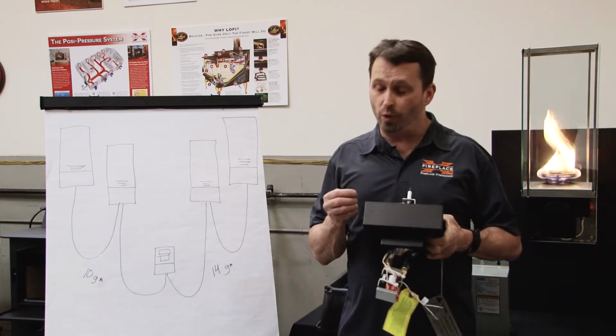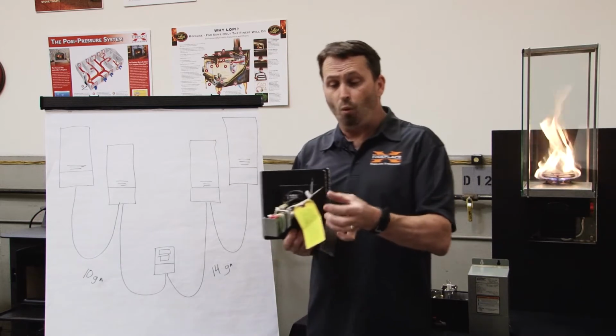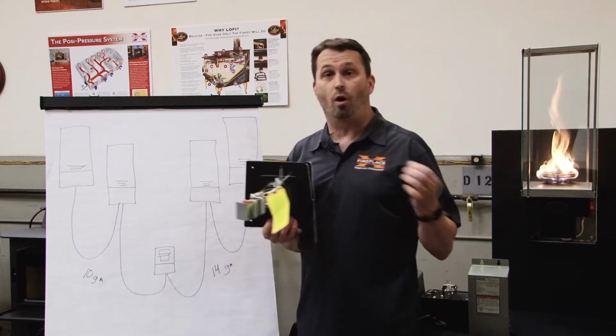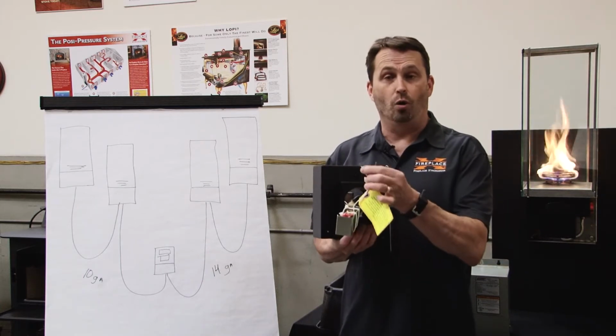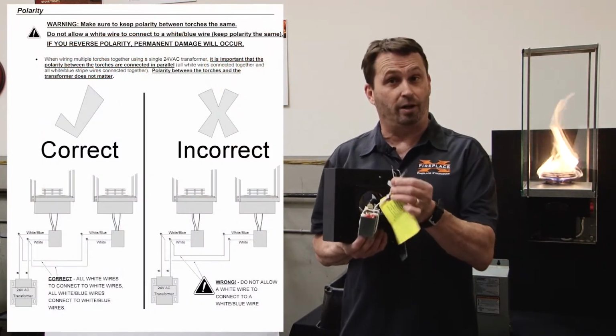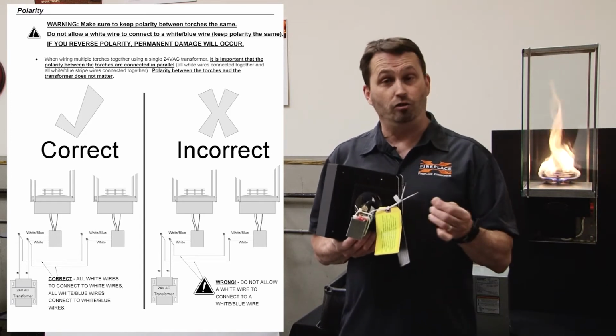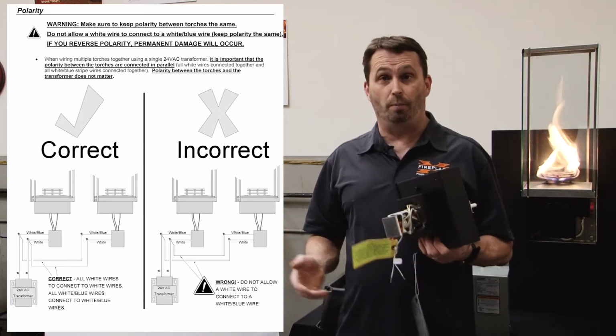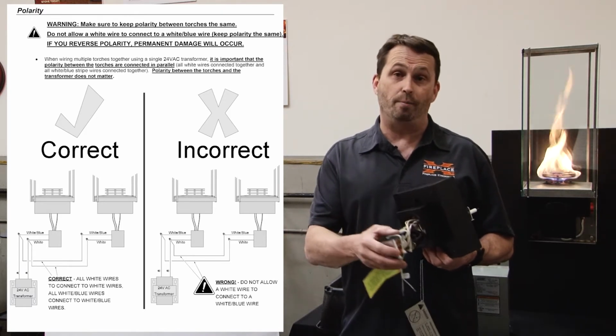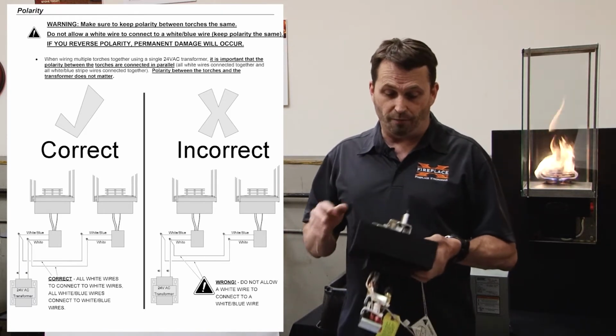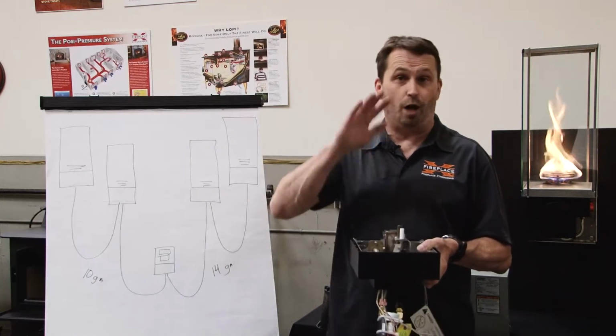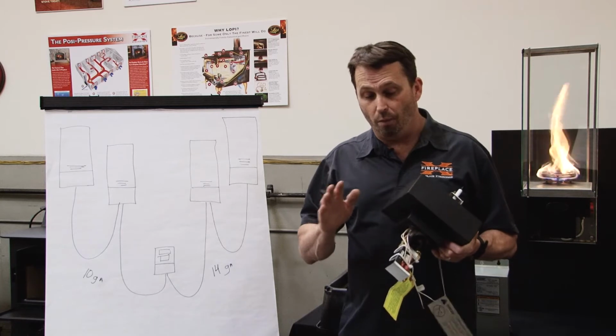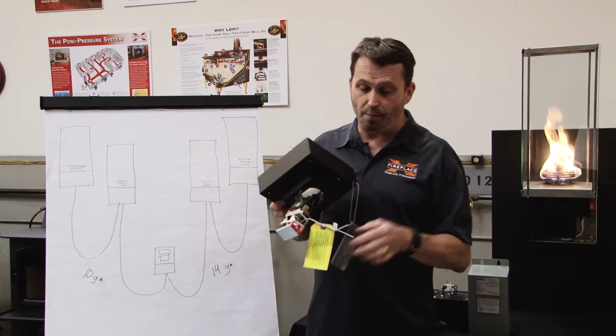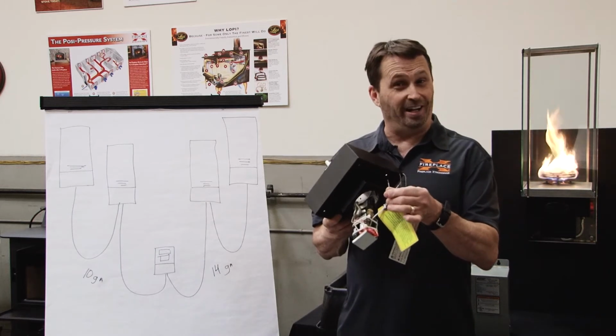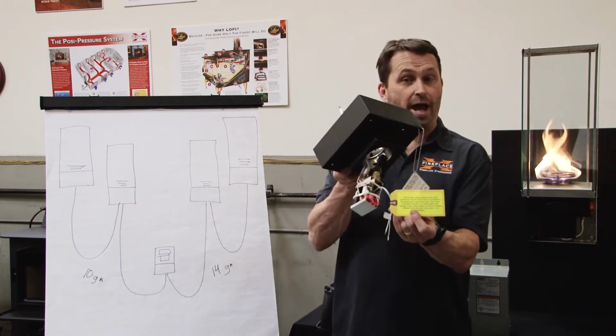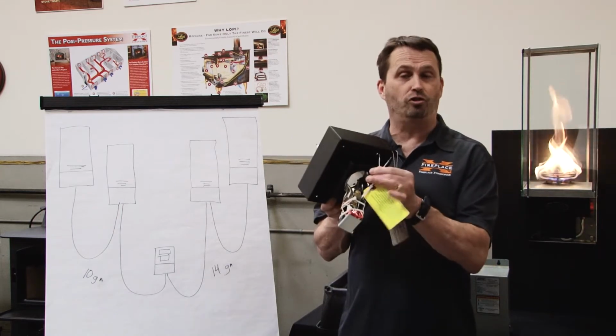So it's absolutely critical that whichever way these get hooked up to the transformer, all the torches get hooked up the same. So the white wire and the white blue wire never come in contact with each other. If they do, once you apply power to the service, you're going to damage the internals on your control module. The first symptoms of that, the torch will probably start cycling up and down and eventually quit working altogether. But we don't want to do that, so just keep in mind polarity is critical. This neon tag right here is a single statement just about the polarity.